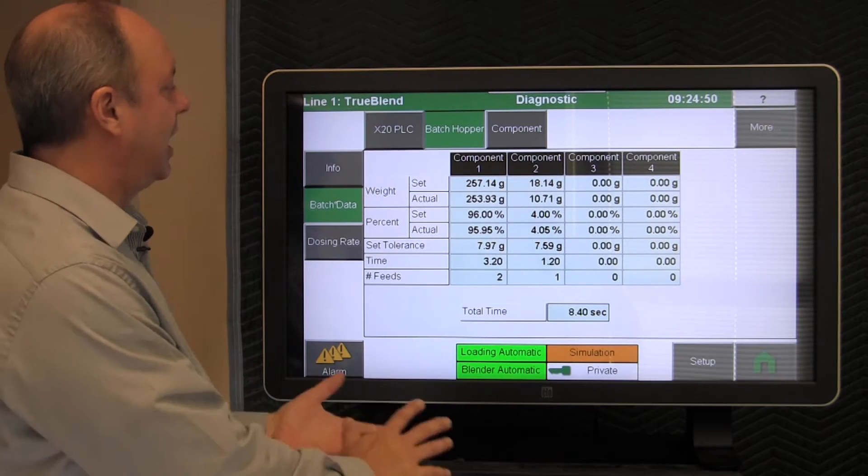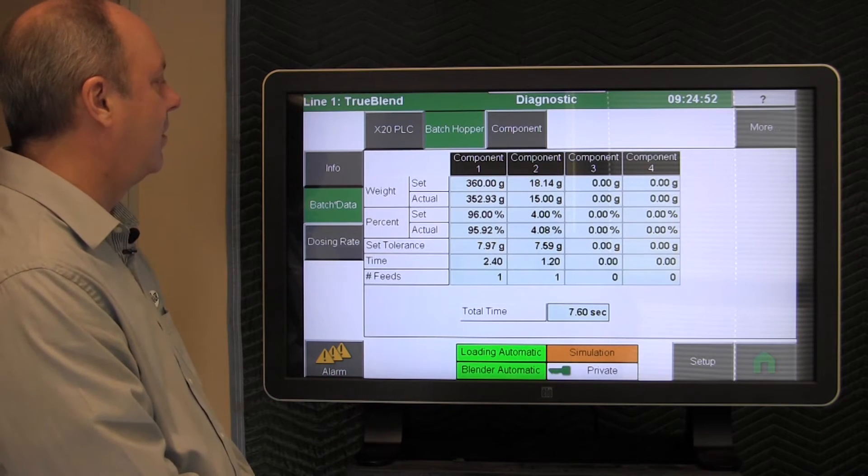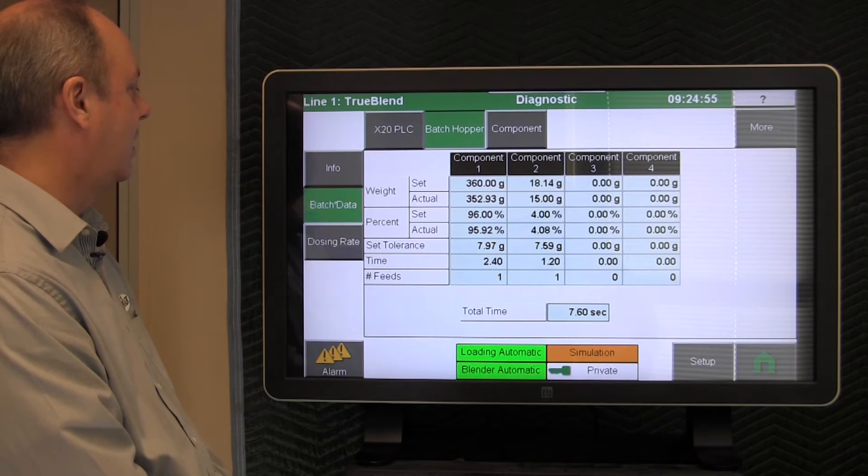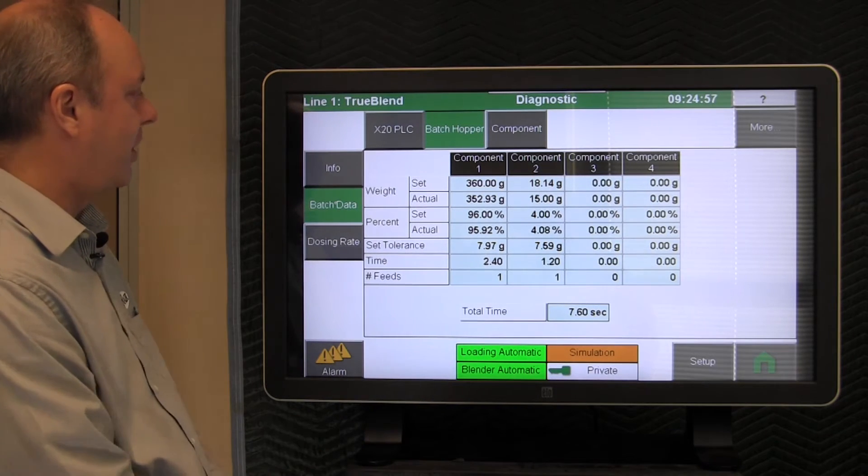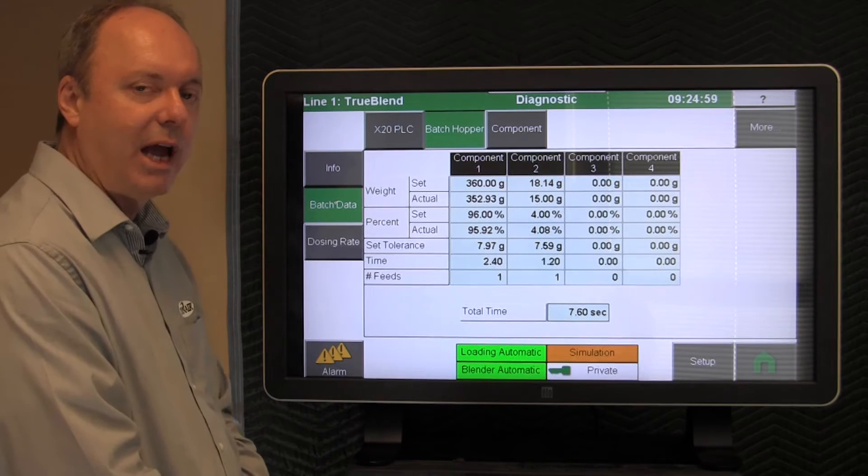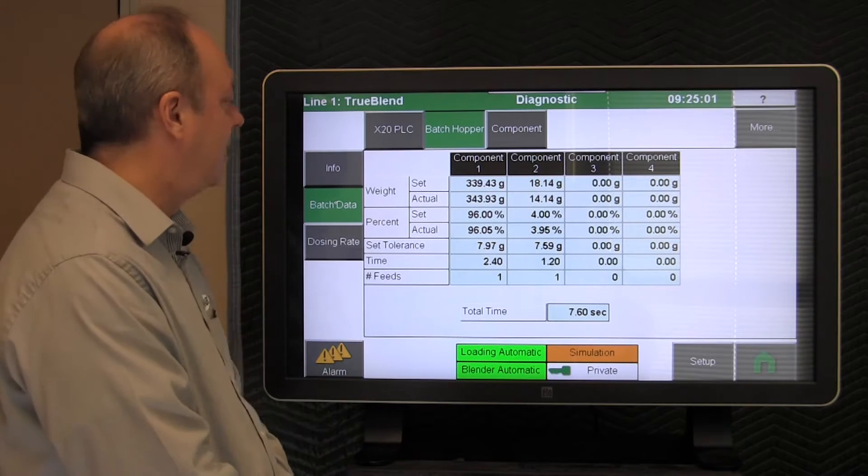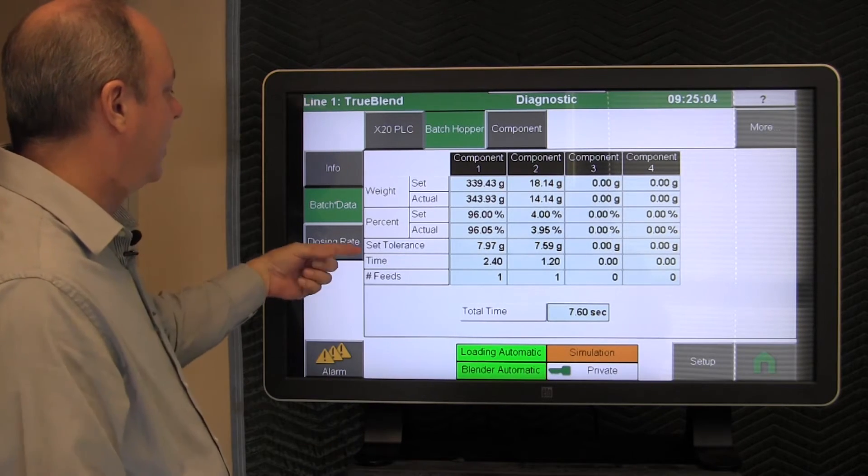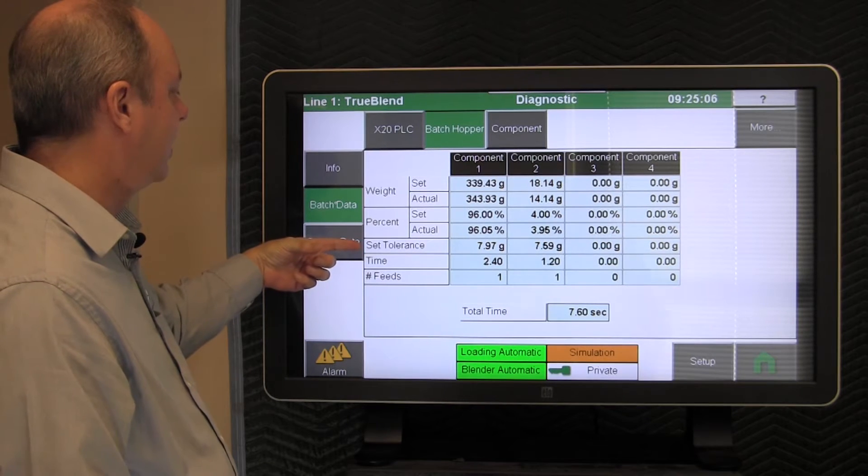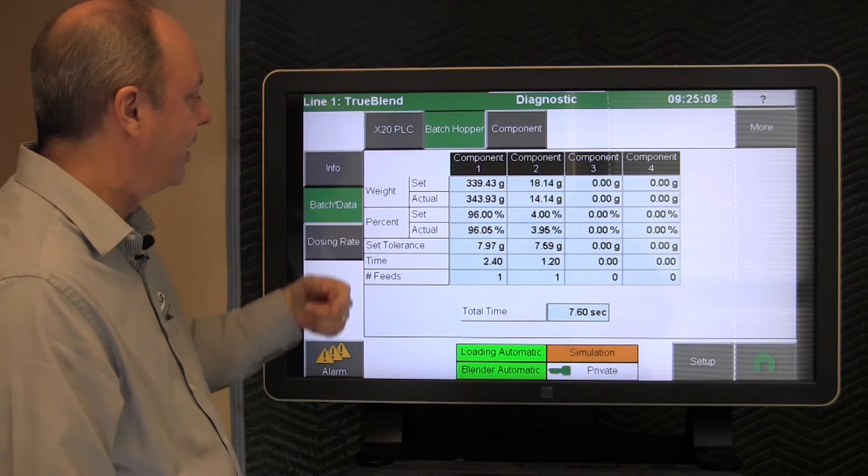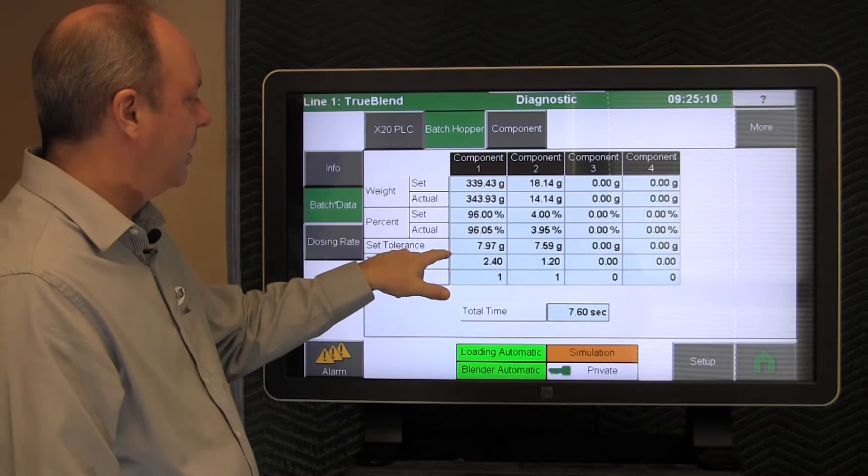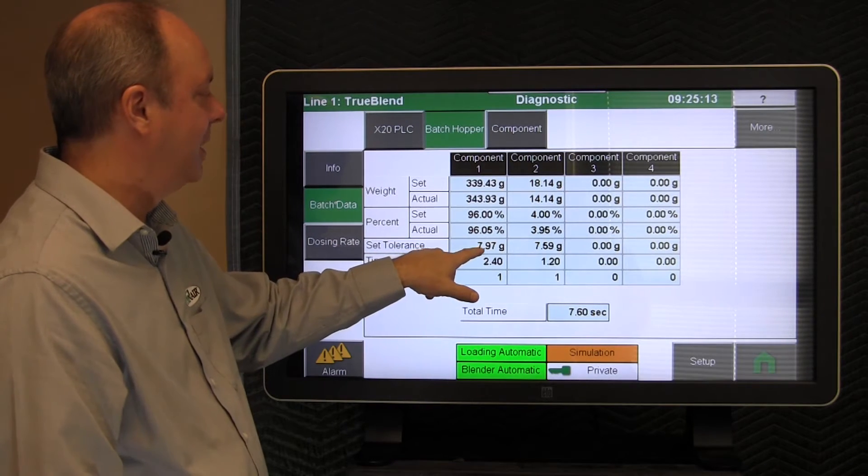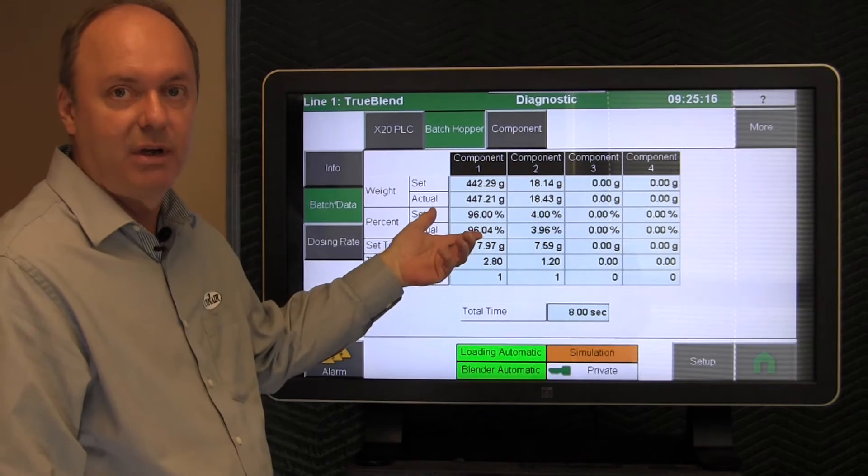So this helps you diagnose exactly where to go and to look on the blender. Before we leave this screen and start testing the blender itself, the outputs and the different components within the blender, let me explain. This particular line here is called set tolerance. This is the computer's calculation for the minimum amount of grams that that valve can dose.